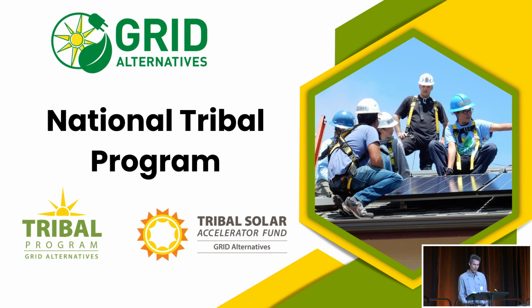Another topic on the list was decommissioning strategies. This applies when an older solar system is failing, which we see from time to time since the solar industry moves quickly and equipment is replaced often. Systems installed 10 or 20 years ago often have obsolete equipment, so you can't find replacement panels or inverters. If a system has totally failed, you're looking at decommissioning that site. In my mind, it's really a decommission and retrofit, where you hopefully reuse the existing infrastructure, like the point of interconnection and the AC side wiring, and just add new equipment.